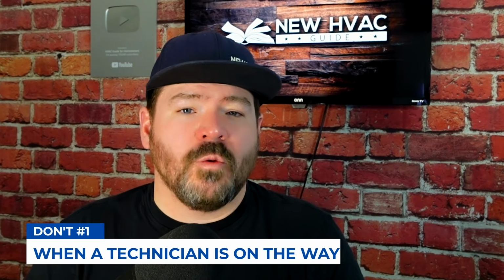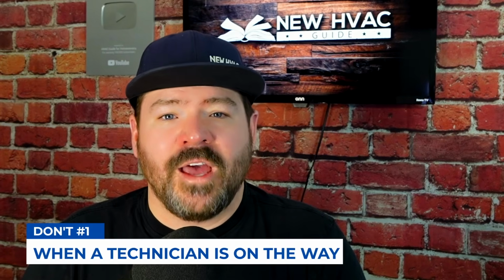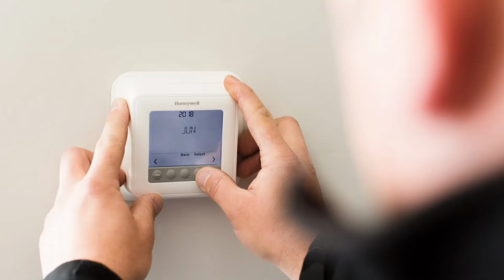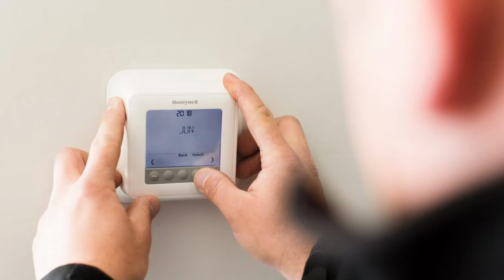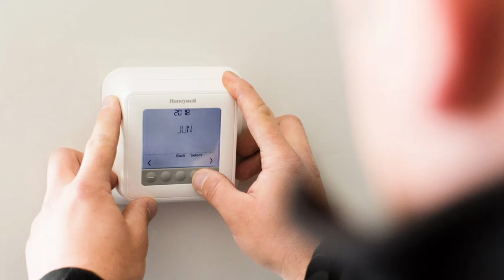Now let's talk about the times you do not want to reset that system. The first one is when you have a pro on the way. When a technician is on the way, whatever that timeline is, resetting the system may clear out an error code. Some systems, resetting it clears the history and we lose it. A lot of systems, especially higher end ones, I can go in and pull a history. But some systems I can't.